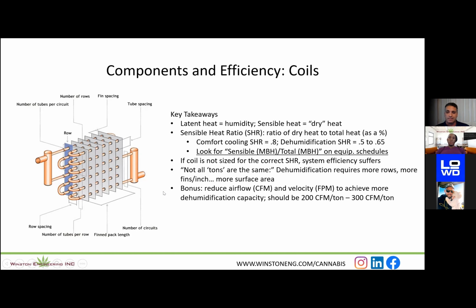So yeah, if the coil's not sized for the correct sensible heat ratio, your efficiency is going to suffer. Again, if you don't have enough depth and surface area on that coil to wring that moisture out, your unit's never going to stop. It's going to continue to operate until it reaches the set point. And if your coil's not sized right, it won't reach the set point. So you'll be burning energy and you will never get to the set point you want.